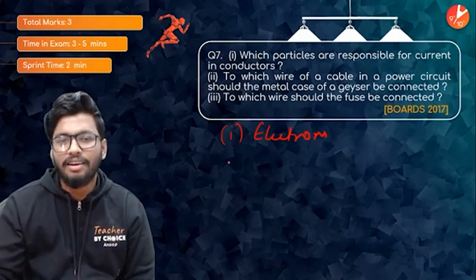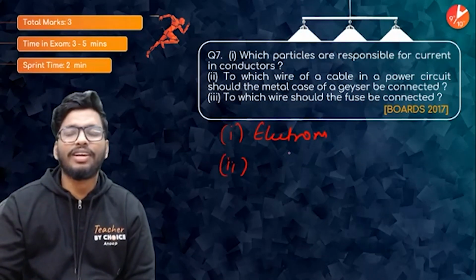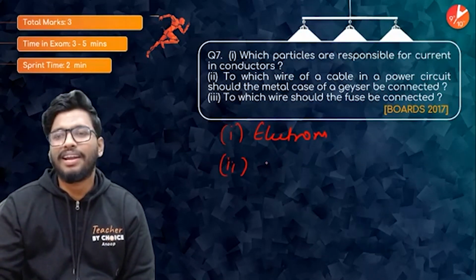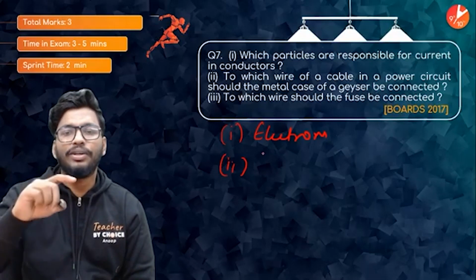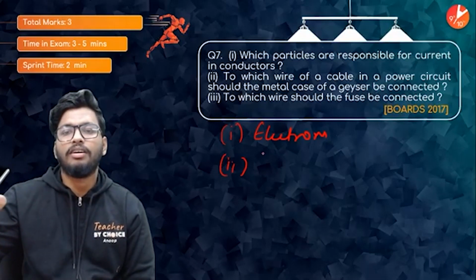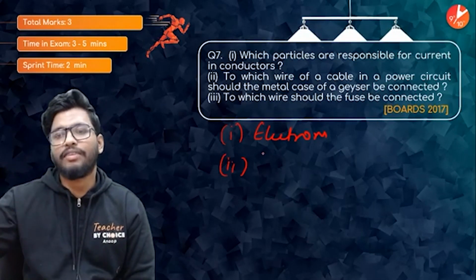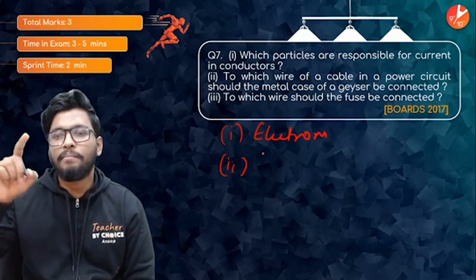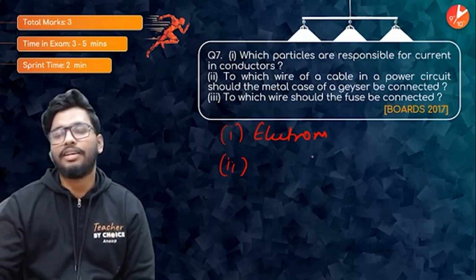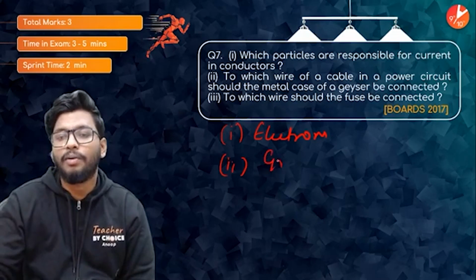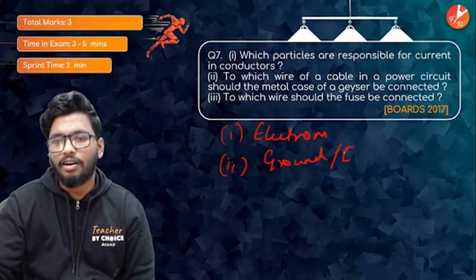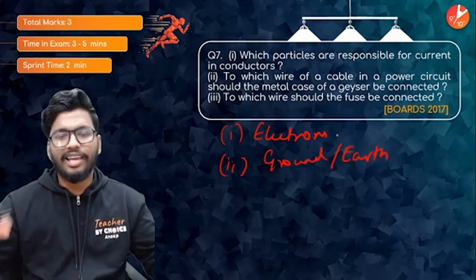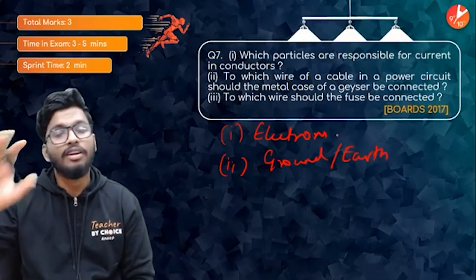Second one: to which wire of a cable in a power circuit should the metal case of a geyser be connected? It should be connected to the ground wire, or the earth wire. The metal case should be connected to the earthing wire, because when you touch it, you should not get electrocuted.